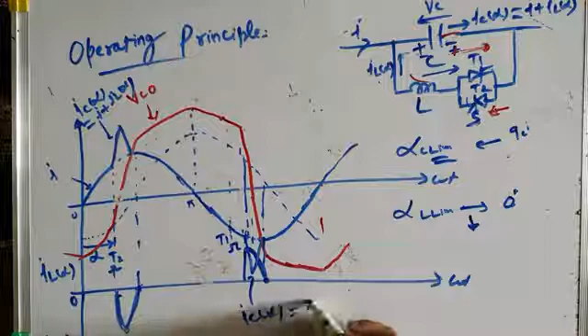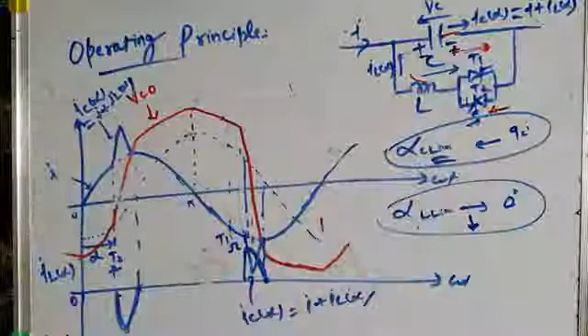If the delay angle range is alpha L lim to 0 degree, then you will get similar waveforms, I mean variable voltage, but that voltage will be inductive voltage. Your TCSC will operate in the inductive mode of operation. So for this range of delay angle, it will operate as a variable capacitive reactance, and for this range of delay angle, it will operate as a variable inductive reactance. So this explains the operation of TCSC.